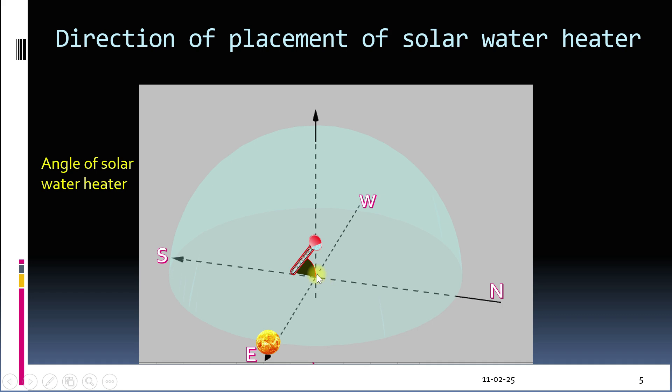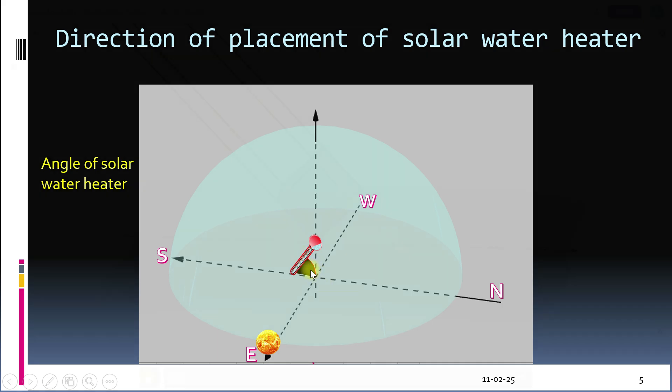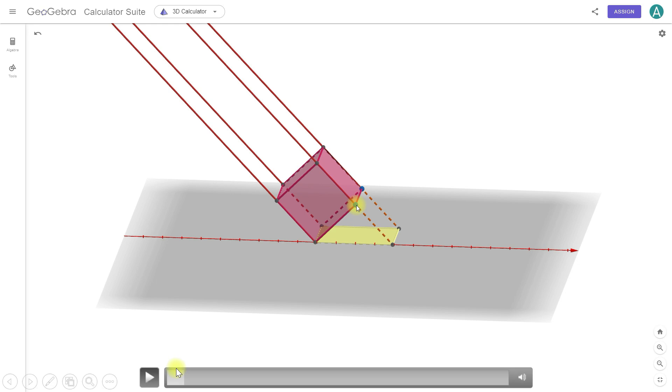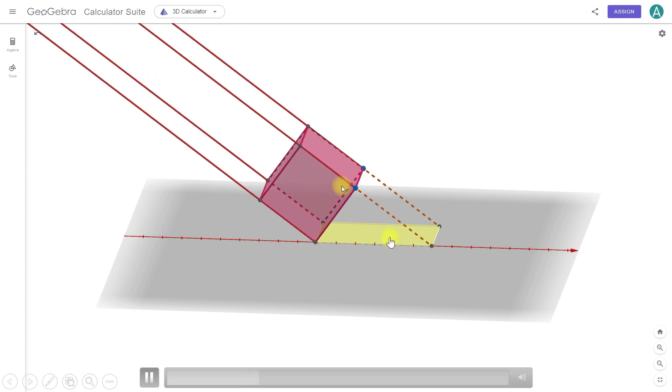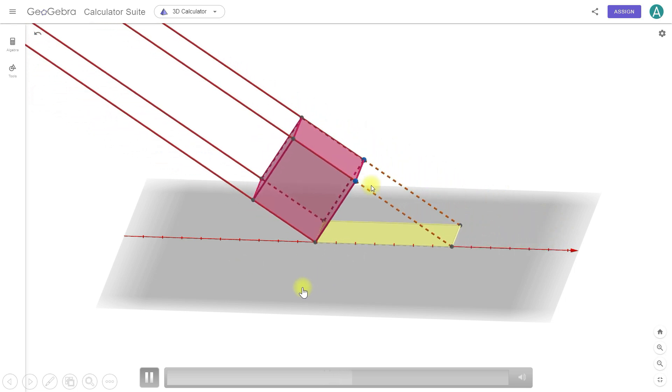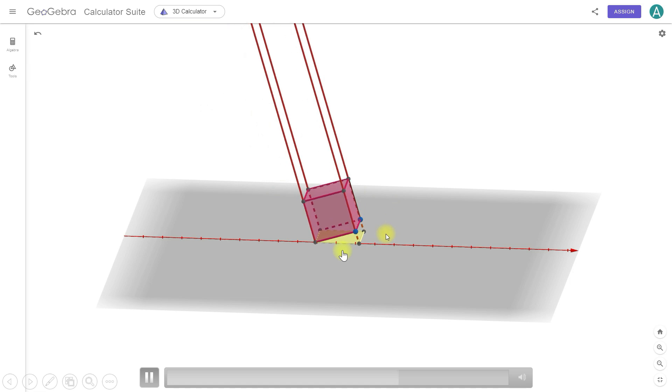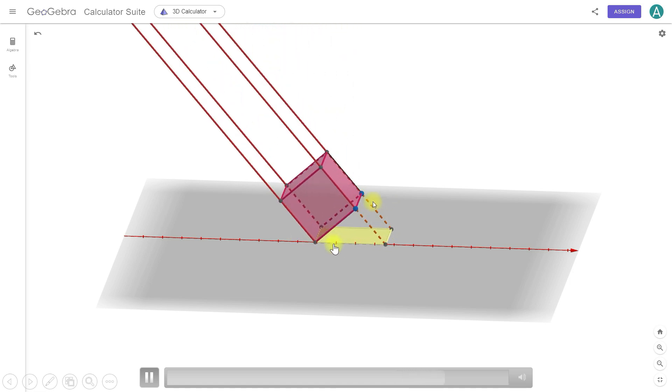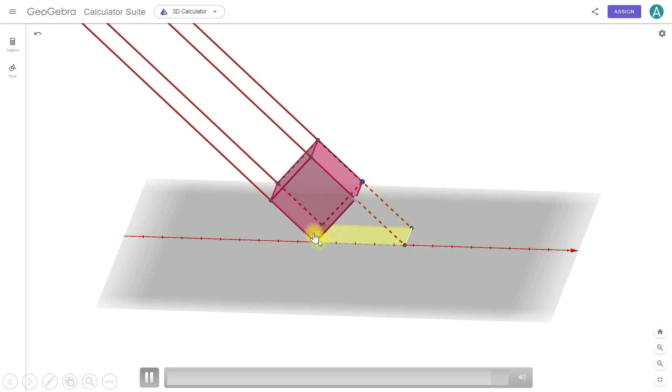But direction isn't the only factor. Angle also plays a crucial role. For maximum efficiency, the solar rays should hit the collector surface at a 90 degree angle. If rays hit at an angle greater than 90 degrees, the energy spreads over a larger area, reducing its intensity. As I adjust the angle here, you can see the illuminated area, shown in yellow, grow larger. This means the same amount of energy is spread over a bigger area, reducing the energy per unit area. So to get the most out of a solar water heater, the collector surface should always be perpendicular to the sun.